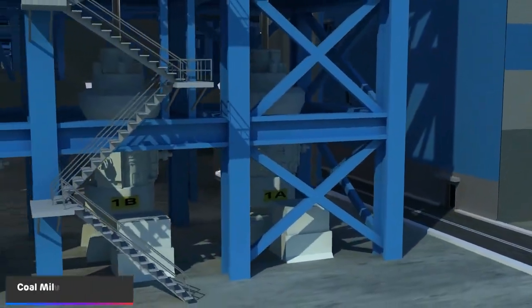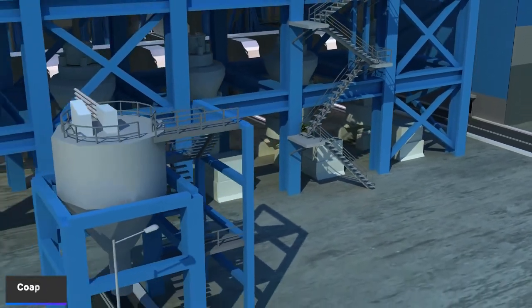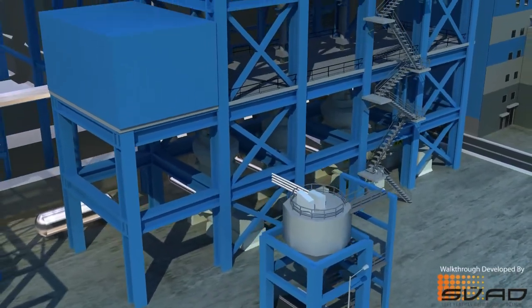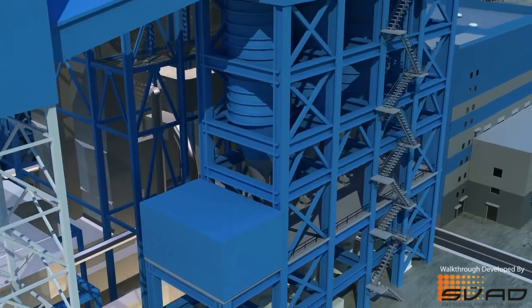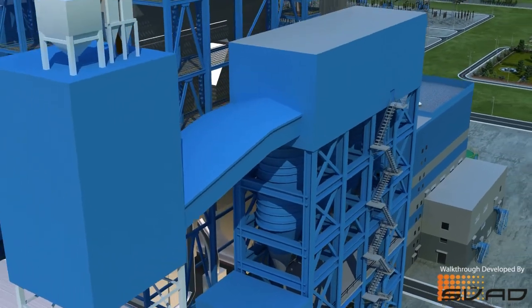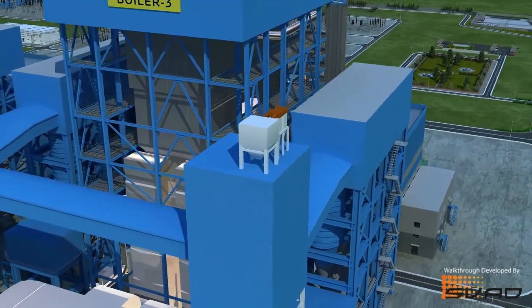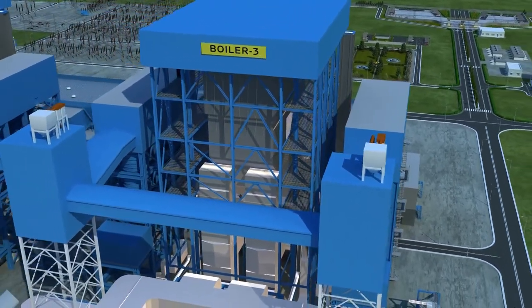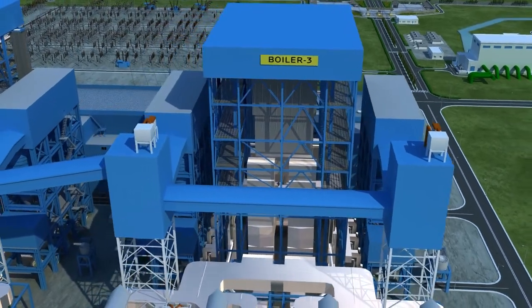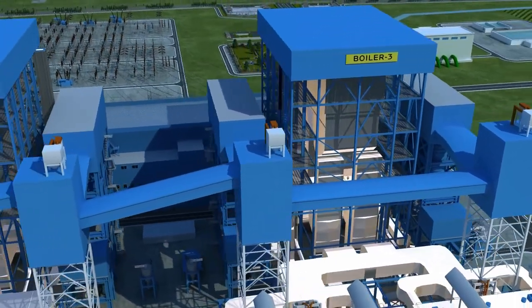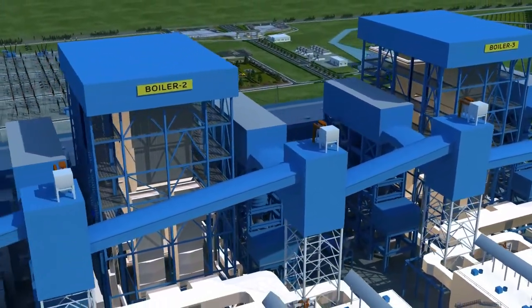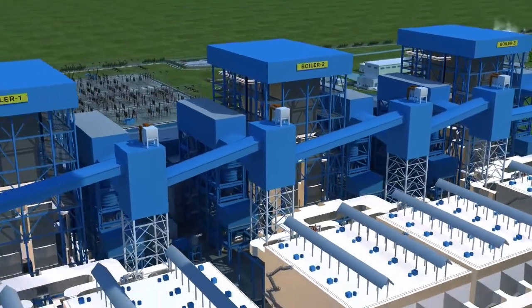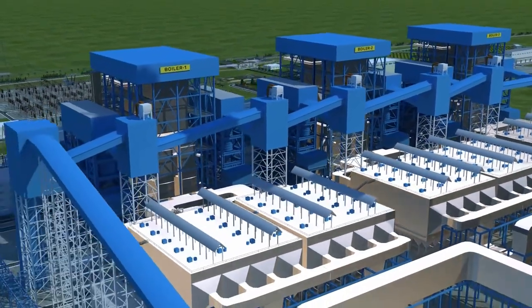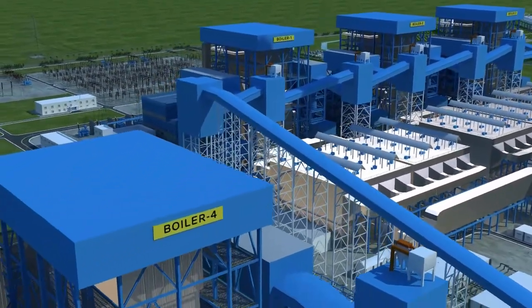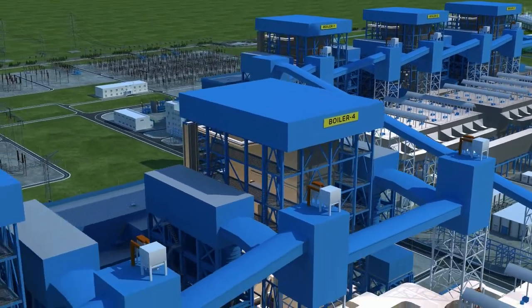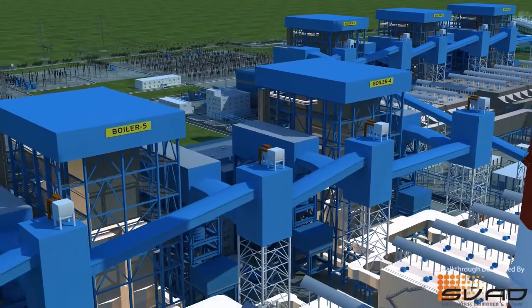The coal mills finely powder the coal, and then it is fed through burners into the boiler furnace. The main plant equipment, comprising the boiler, steam turbine generator and its auxiliaries, has been supplied by Messrs. Shanghai Electric Corporation, China. Each unit of the plant has its own boiler, also known as steam generator. Each 660 megawatts boiler can convert more than 2,111 metric tons of water per hour into high pressure and high temperature steam. For a 660 megawatt unit, the steam is generated at 250 times the atmospheric pressure, and the temperature is as high as 570 degrees centigrade.